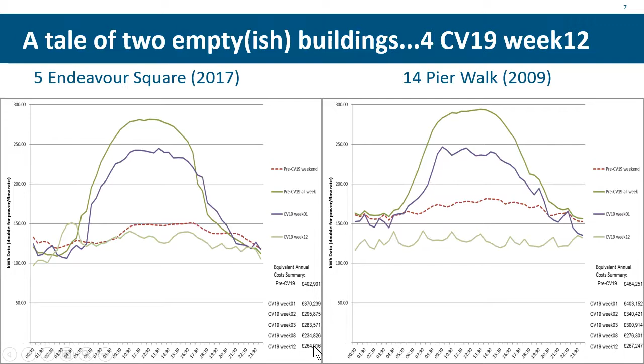that weekend average in both of them. In fact, at Pier Walk, we've dropped below. What we're seeing here, I think, is security walk-arounds still happening and bringing on lights. That's what those peaks are, because the lighting systems come on for 20 minutes and then drop away. But we're still sitting at around 260,000 pounds a year. So over £500,000 a year's worth of electricity for circa 30 people.